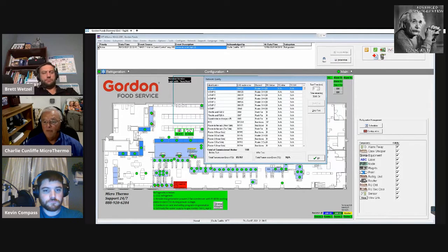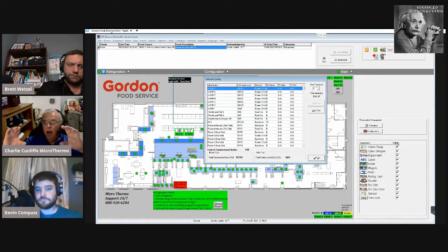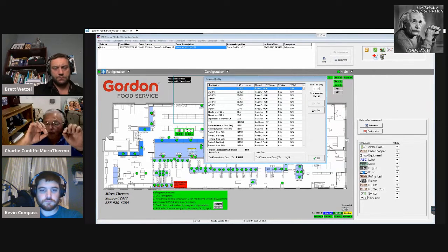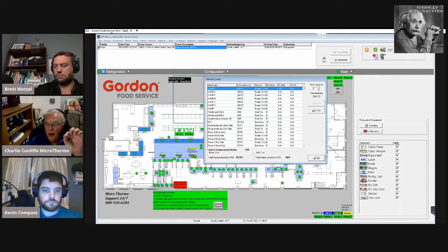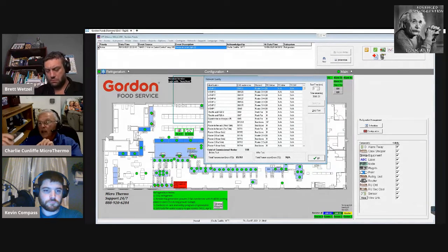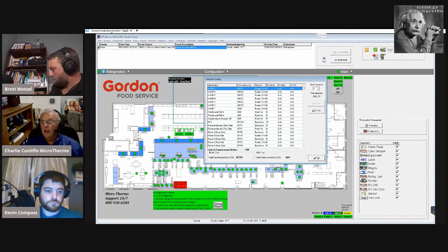I really don't have that happen very often, but if I was doing the full Micro Thermo class and it was a simple 508 board, there are test points where you can check, okay, I've got 24 volts coming into the board. Now, some things like simple switches and thermistors need the 5 volt circuit. So there's a point on the board for ground and another 5 volt test point, and you can see, do I have a 5 volt circuit? Yes or no? Then transducers and complex devices like a combined temperature and RH might need 15 volts. There are other points where, again, ground and 15 volts, and you can make sure that you do, in fact, have 15 volts present on the circuit that is supposed to power those complex devices.